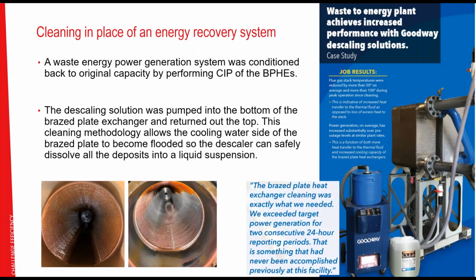Another one. Another of these cleaning in place examples is for a completely different application. It's a waste energy power generation system, again operating with high water temperatures. Again, scaling is an issue, and by cleaning it out, we went from a dark reddish brown. This is not the copper you see here. This is bad stuff, right? Even if scale is a white salt, since it absorbs the solids, it always looks a little bit brownish. After cleaning, you could see yourself in the reflection again.